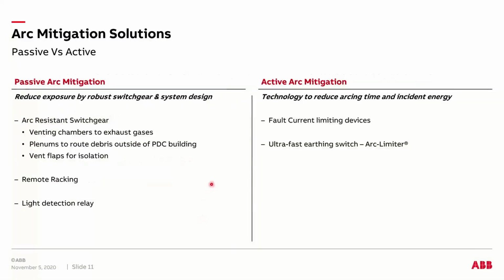So let's look at some of the other methods that are popularly used. We categorize them into two different arc mitigation technologies. One is called passive arc mitigation, and the other one is active arc mitigation. When we call it passive, we are not really clearing or stopping the arcing fault from occurring. We are using, for example, chambers or plenum to safely exhaust any kind of debris that could form due to an arcing flash within your equipment, and safely route it outside of your e-house or PDC building. The other one is a remote racking device, which is also very popularly known and utilized.